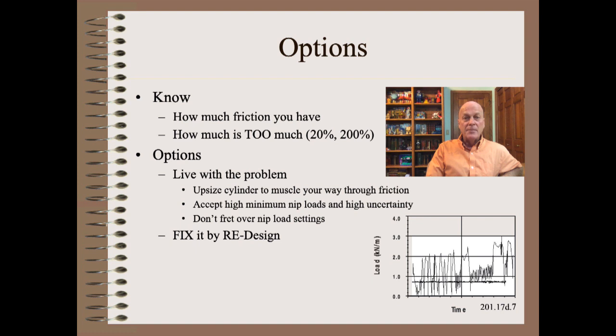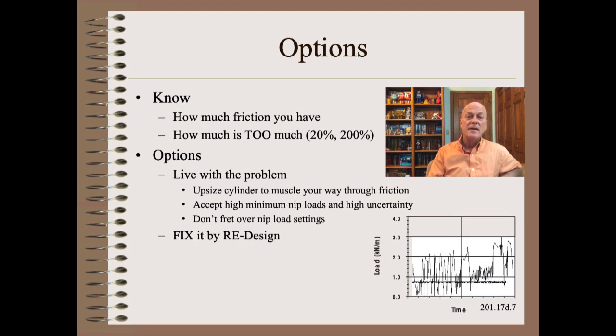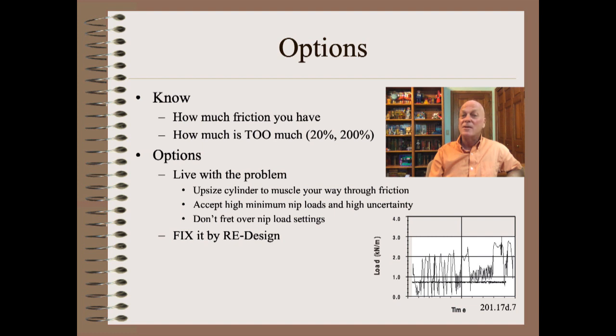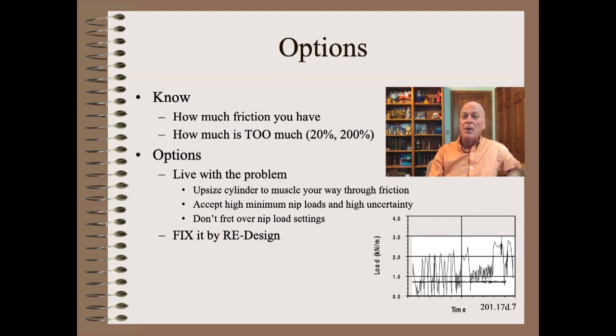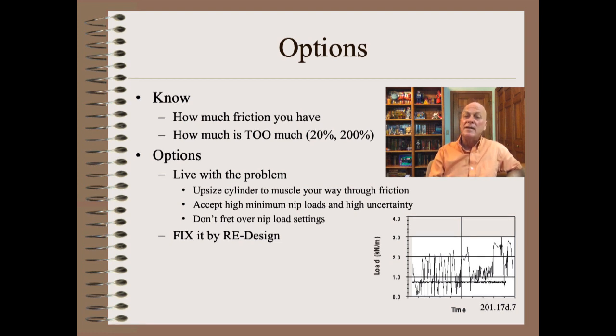Before you consider your options, you need to know two things. First, how much friction you have, by the measurement methods described in previous clips. Second, how much is too much? Is 20% too much? Or can you take 200% because the application is tolerant? Laminating nips and kraft paper winding nips are usually tolerant, while tissue nips never are. If we decide we have too much friction, we have two options: the first is to live with the problem, and the second is to redesign the nip loading system in very specific ways.